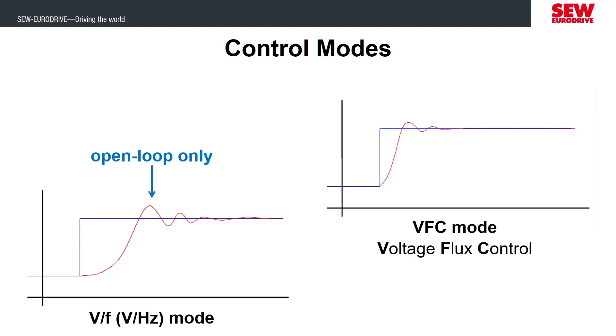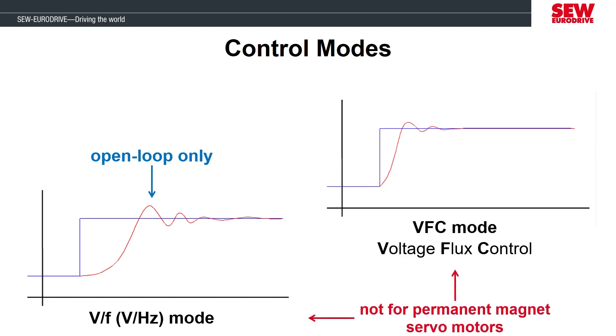VFC mode stands for Voltage Flux Control, which switches on the ability of the MOVIDRIVE to determine the orientation of the magnetic fields in the motor and apply the three-phase voltage appropriately to control the magnetic field. VF or VFC modes are only for asynchronous motors — these will not work for permanent magnet servo motors. There is a specific servo mode that has to be used when operating permanent magnet motors. Since VFC is for asynchronous motors, it can be used with or without an encoder. In our lab today, we are using the encoder signal to improve the speed control accuracy.